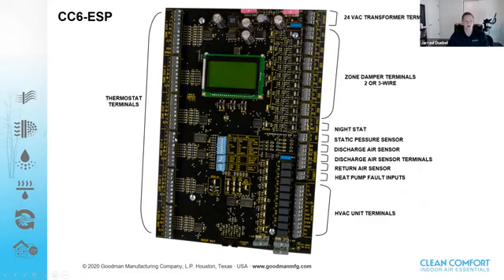We took that off of next to the zone thermostat, and we actually built that into the display on the 6-zone, so you can just select which zones are going to do the bypass free option. And if you enhance it to a 9 or 12-zone system, it automatically brings those zones up. There's no additional programming or anything like that needed. Additionally, you can set your high and low discharge air limits all through the display. You can turn your upstage timer on and off if you'd like to.